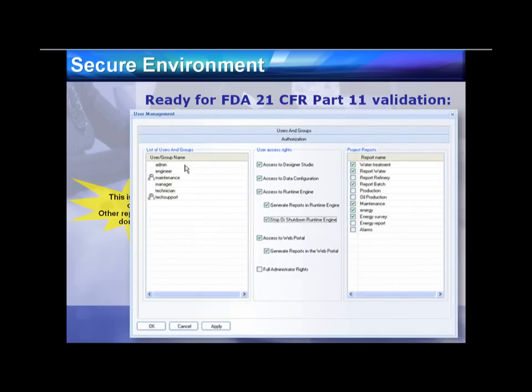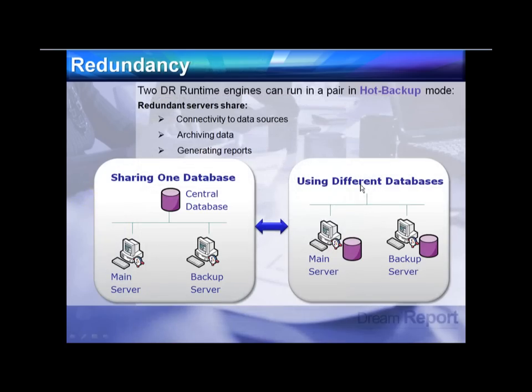Security controls extend down to which individual reports each user or group can access. DreamReport can also run in a redundant pair or hot backup mode, giving higher availability — two nodes may both log data into a central database, or each maintain its own logging database kept in sync on a fixed interval, transparent to the user.